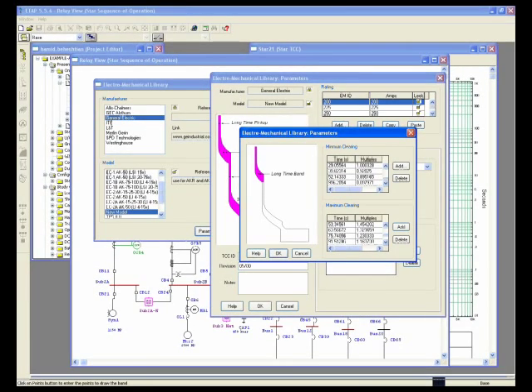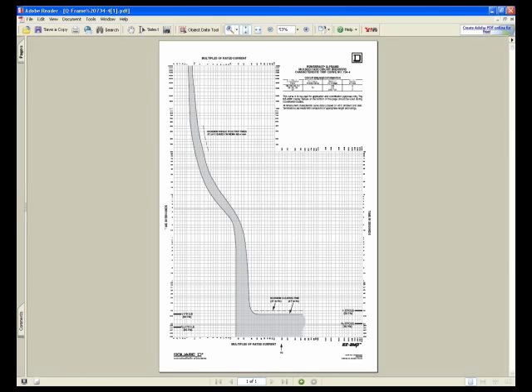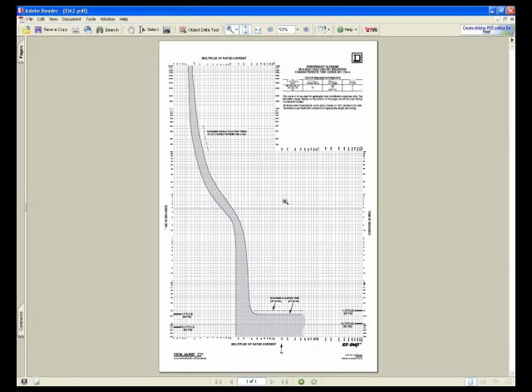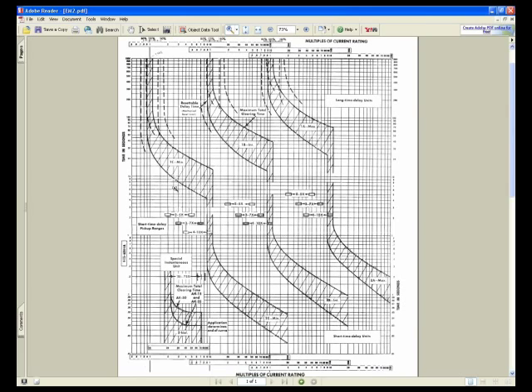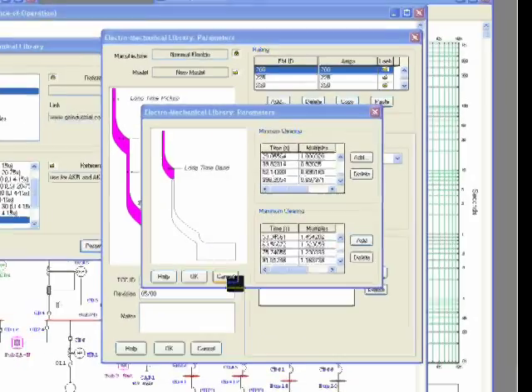This is a sample curve for EM trip device. As you can see, it has a long time and there is a long time band. There is a short time and there is a short time band. They can be adjusted to the left and right, and ETAP can handle this editor.